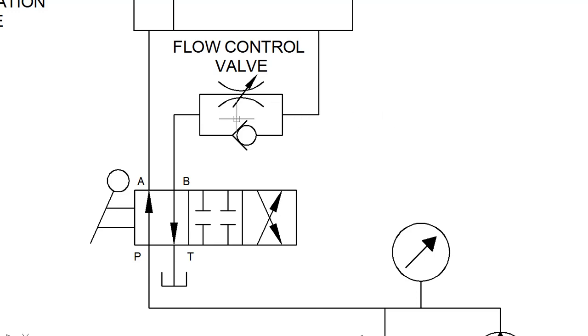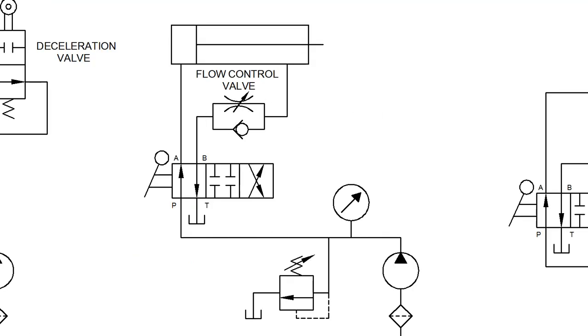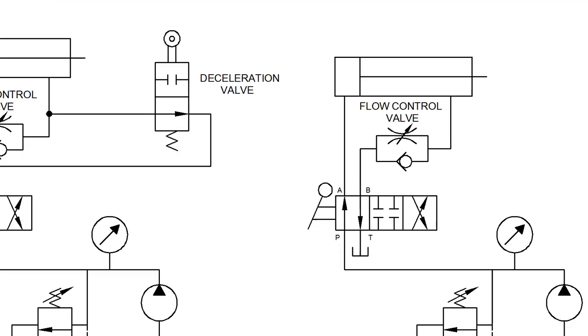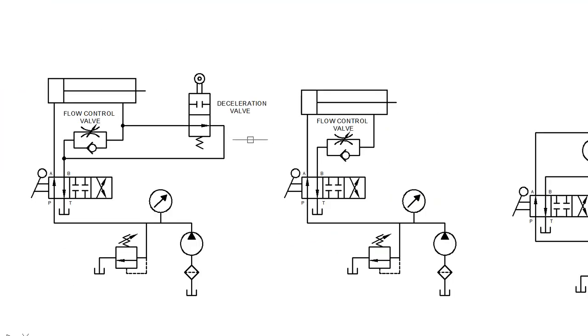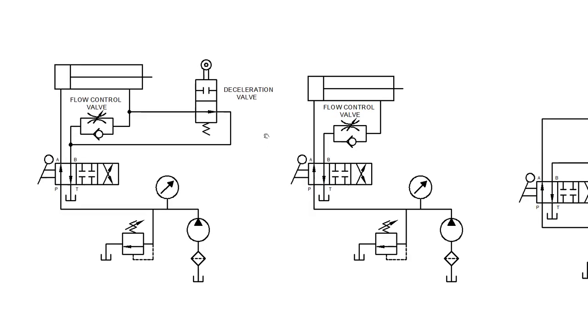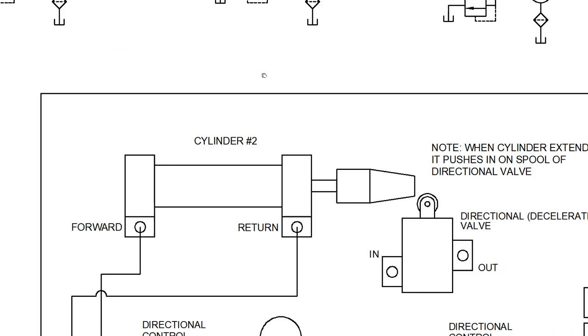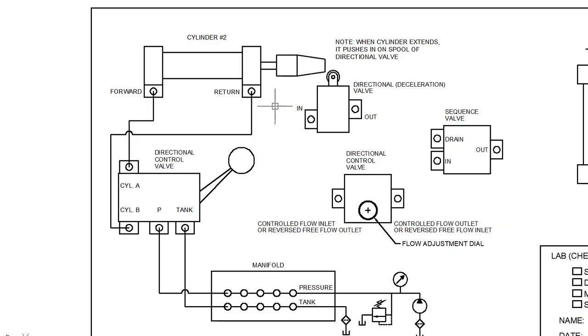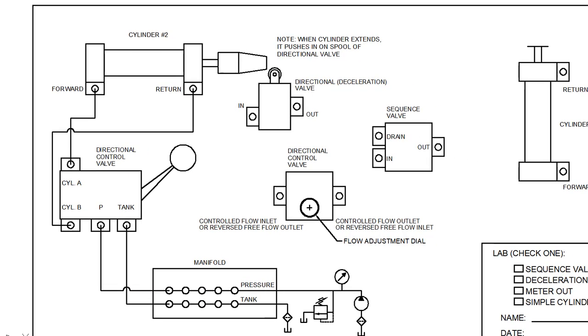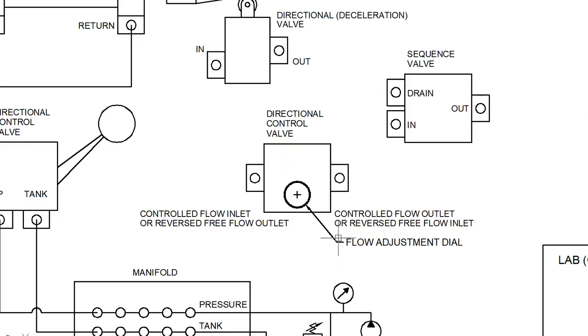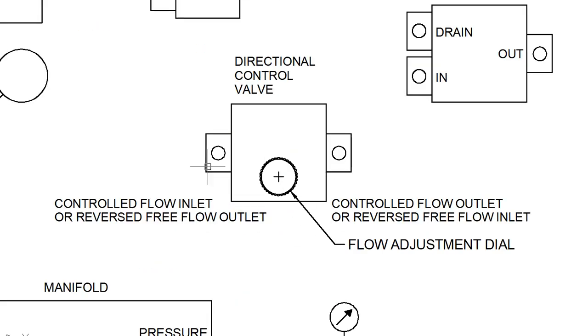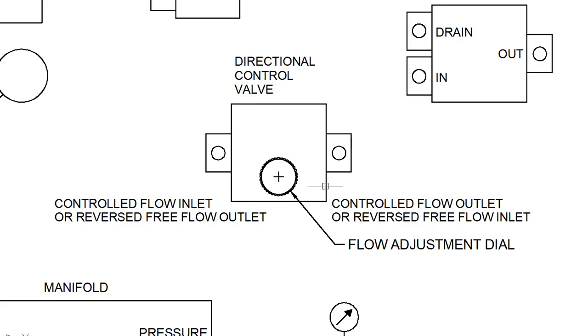This inlet and outlet—make sure that you figure out which side is the inlet, which side is the outlet. I've tried to put on here essentially the information that you will find on the actual trainer. This would be like a catalog, and the catalog would tell you that this inlet is a controlled flow inlet, or you can consider it the reversed free flow outlet. That's the information you get from the spec sheet, the documentation on this actual valve as opposed to the symbol.